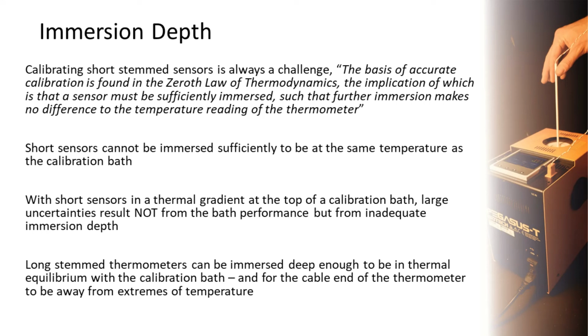Calibrating short stem sensors is always a challenge. The basis of accurate calibration is found in the Zeroth law of thermodynamics, the implication of which is that a sensor must be sufficiently immersed such that further immersion makes no difference to the temperature reading of the thermometer. Short sensors cannot be immersed sufficiently to be at the same temperature as the calibration bath. With short sensors in a thermal gradient at the top of a calibration bath, large uncertainties result not from the bath's performance, but from an inadequate immersion depth.